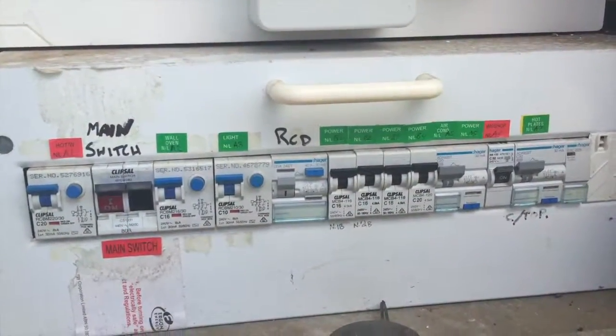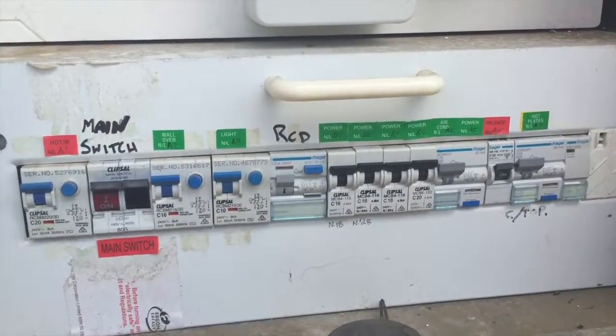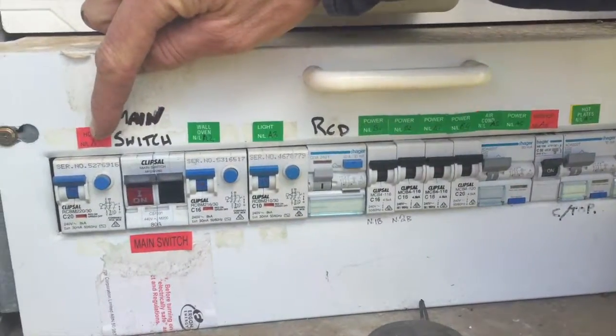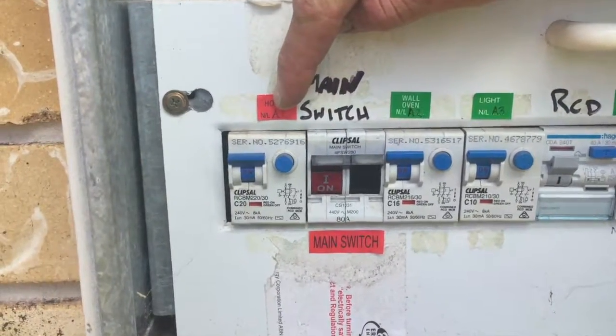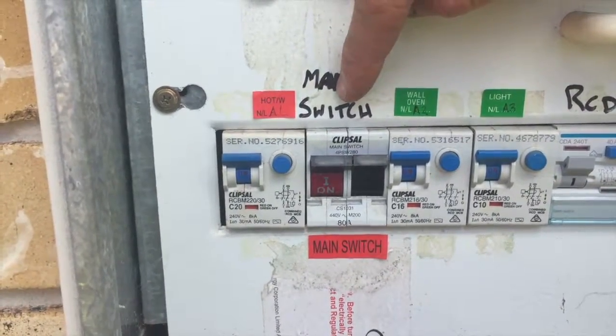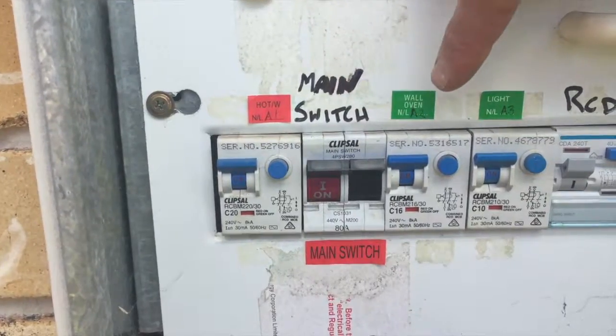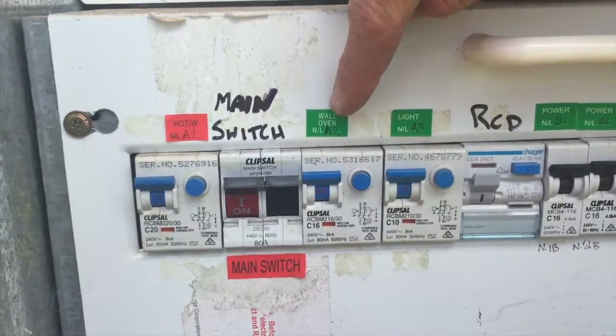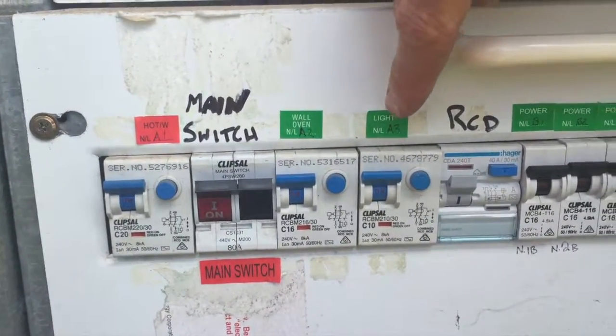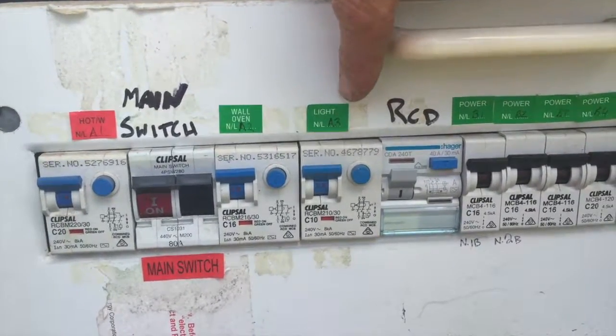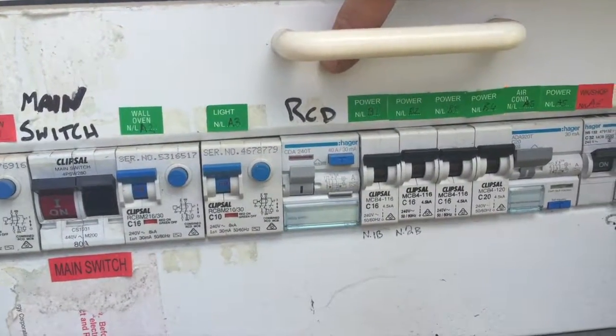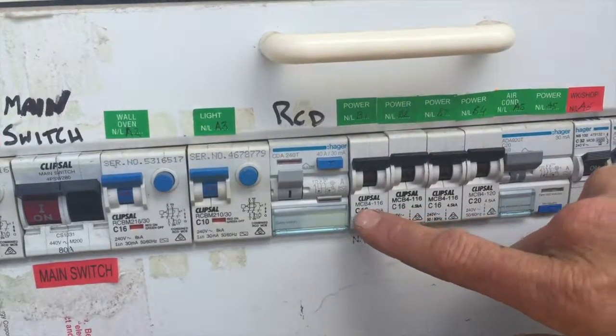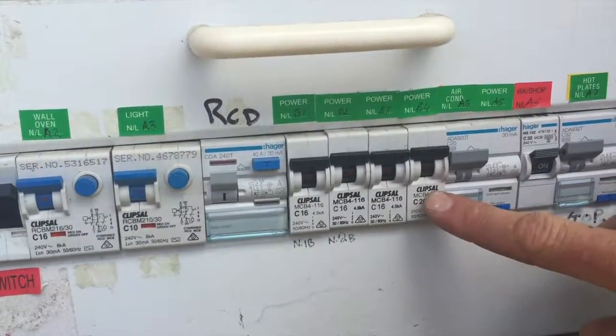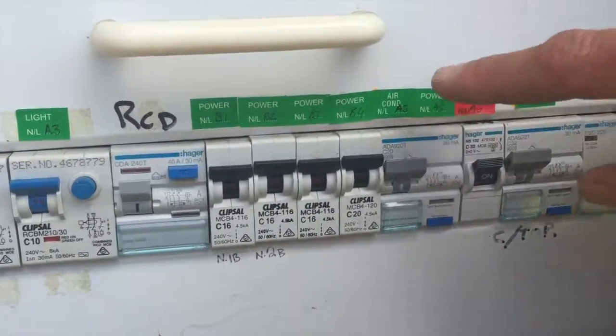This is an example of a very standard switchboard. First, we have the hot water, which is on a combo with its own test button. Then we have the main switch. Second, we have the wall oven on a combo and the lights on a combo. Next we have a safety switch, sometimes called an RCD, which protects the 4 circuit breakers behind it.